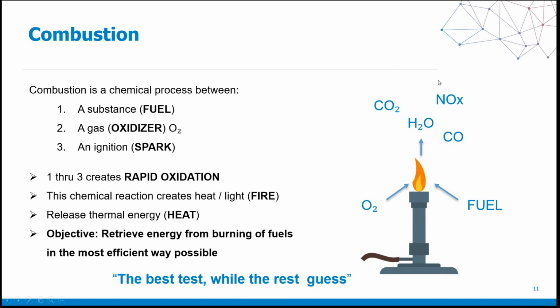And when you do that, you have byproducts that are being created. You're creating CO2, NOx, water, carbon monoxide, fuel, and also oxygen, or in this case, unburned fuel, and also oxygen. And the goal of any combustion process is to retrieve the maximum energy from the burning of those fossil fuels in the most efficient way possible. And unless we are performing a combustion analysis and using a combustion analyzer, we don't know what levels and what concentrations of byproducts we're producing.